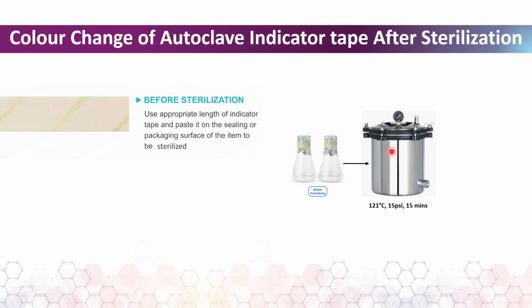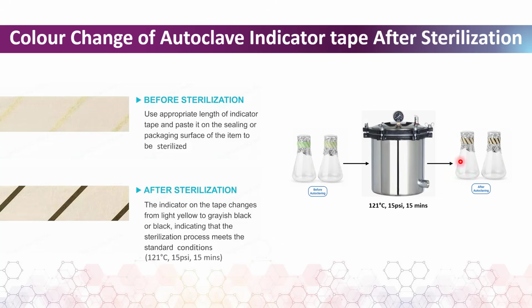For the sterilization to be complete, we allow the autoclave to attain the standard condition, which is a temperature of 121 degrees Celsius and a pressure of 15 psi for 15 minutes. Once these standard conditions have been attained, then we can say that sterilization has been done. After sterilization, the indicator on the tape changes from the light yellow or green strip to grayish black or dark black, to indicate that the sterilization process has met the standard conditions, which is the temperature of 121 degrees Celsius and a pressure of 15 psi for a duration of 15 minutes.